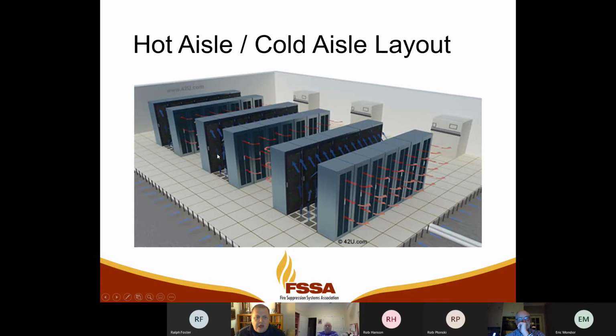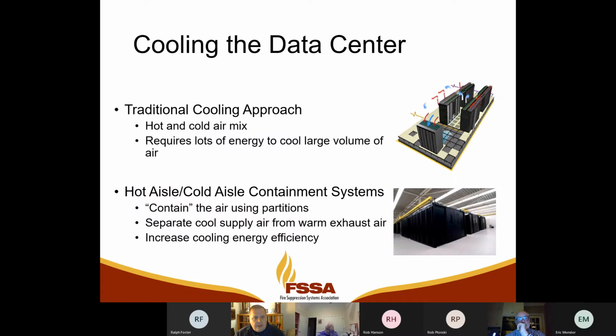So that cold aisle, hot aisle arrangement wasn't always done in data centers. It's a fairly old step now for improving cooling efficiency and effectiveness of the cooling energy used in a data center. Now, we've stepped beyond that in many, many ways. So the traditional cooling approach for data centers was just allowing hot air and cold air to mix. This is a pretty good picture of that.